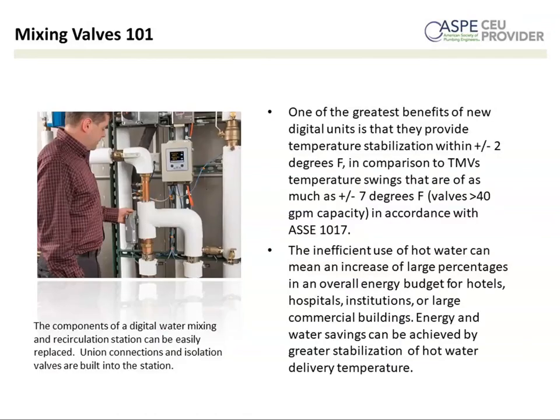So again, one of the biggest benefits around digital mixing is this temperature stabilization of plus or minus 2 degrees. And this was in a previous slide, but it's worth mentioning again that performance of a 4-degree band to set point is much safer than plus or minus 7, or 14 degrees. And again, that ties back to not only safety, also efficient use of your hot water.